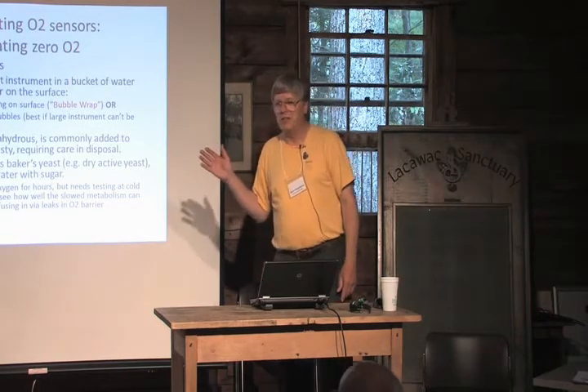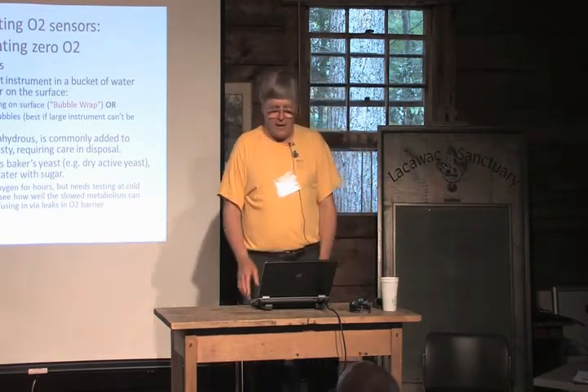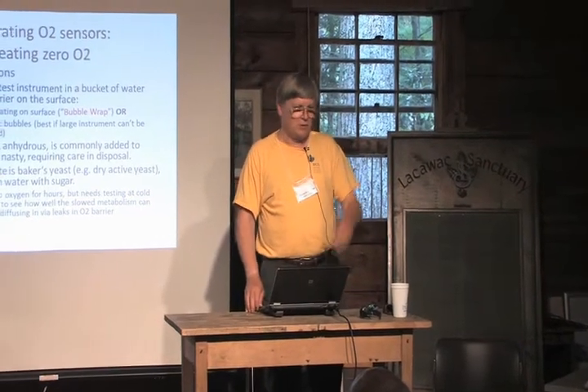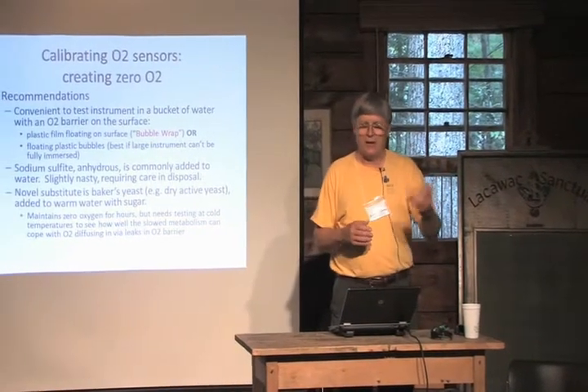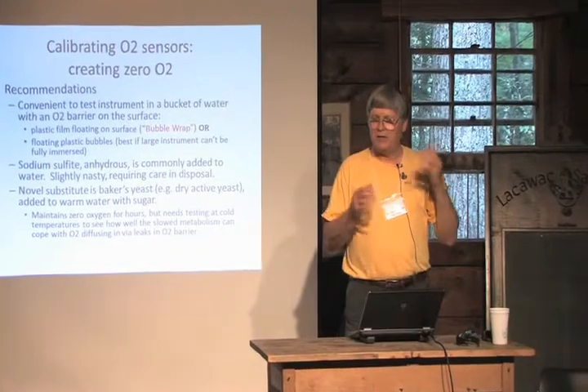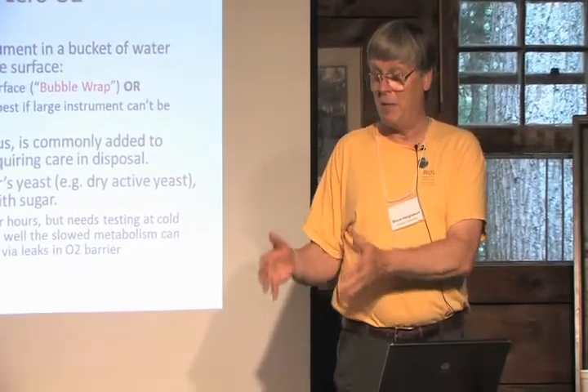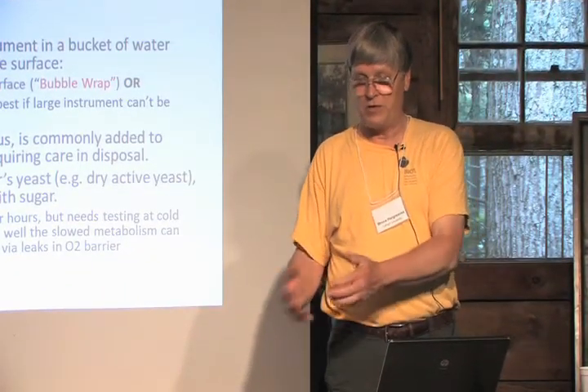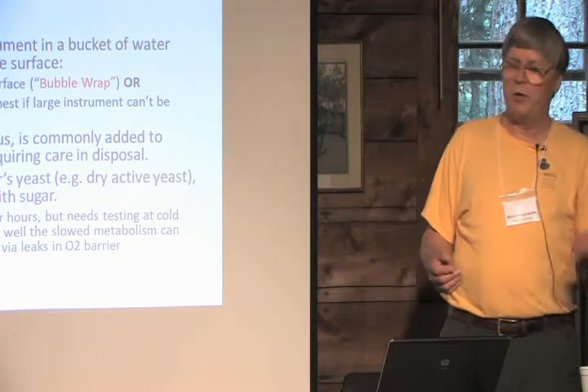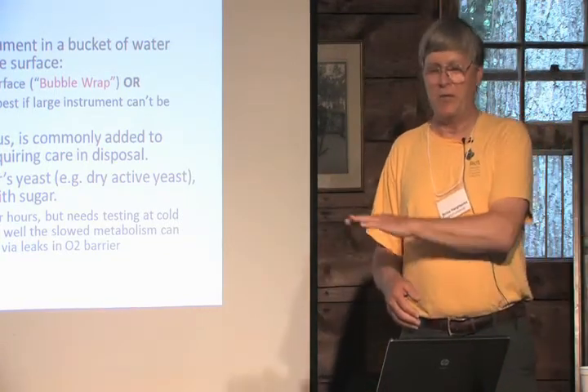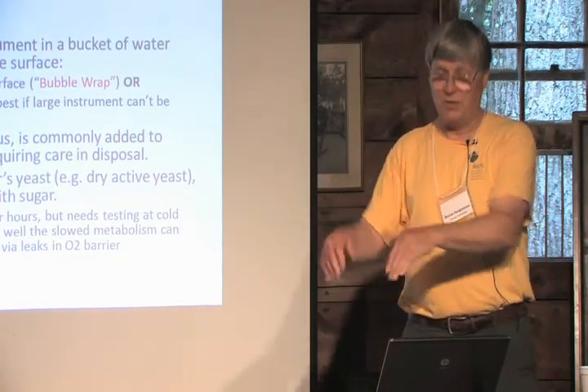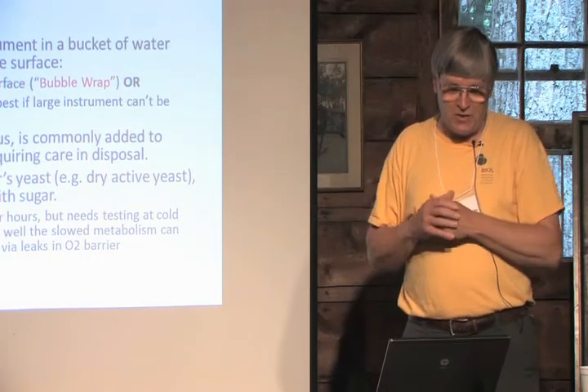Zero calibration is another issue I alluded to earlier. Several manufacturers, including in their manual from PME, suggest putting some sodium sulfite chemical into a bucket of water, in a certain proportion. The chemical absorbs oxygen. You put your probes in the bucket and cover the surface so that no more oxygen is diffusing in. And he suggests a plastic film.